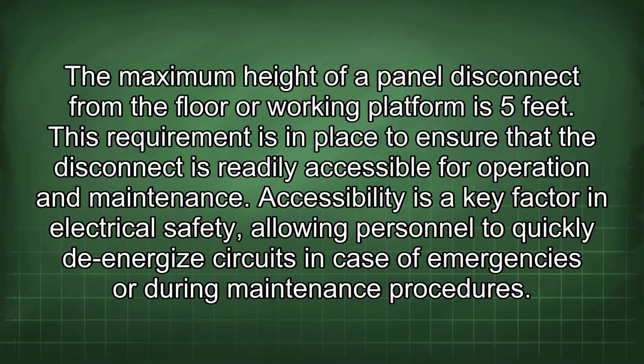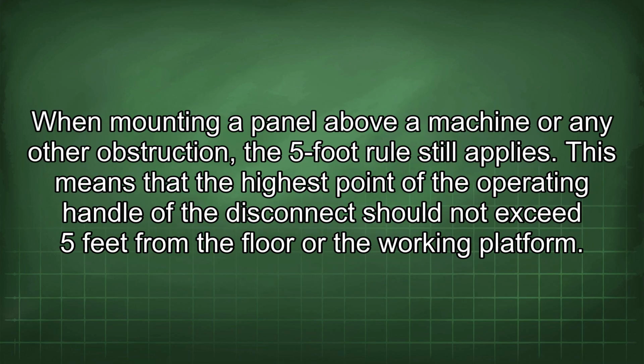The maximum height of a panel disconnect from the floor or working platform is 5 feet. This requirement is in place to ensure that the disconnect is readily accessible for operation and maintenance. Accessibility is a key factor in electrical safety, allowing personnel to quickly de-energize circuits in case of emergencies or during maintenance procedures. When mounting a panel above a machine or any other obstruction, the 5-foot rule still applies.